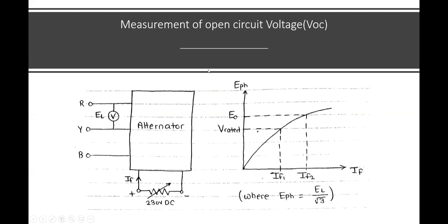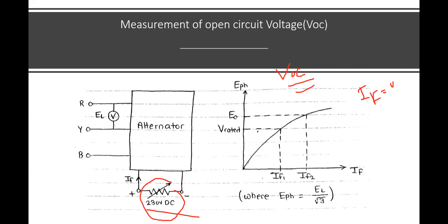To calculate VOC — open circuit voltage — the alternator is given a 230-volt DC supply for field excitation. The procedure is: first maintain field current equal to zero. This is the OCC — open circuit characteristics — which you already learned in DC machines. Initially there is no excitation on the alternator; then start the alternator under open circuit and slowly increase the value of field current.